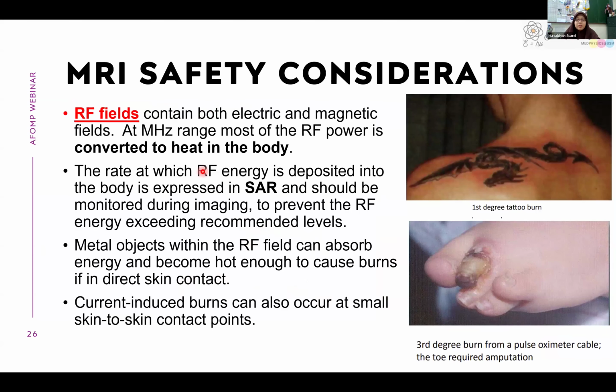In terms of radio frequency, as you know, it is EMF, so it contains both electric and magnetic fields. At the megahertz range, most of the radio frequency power will convert to heat in the body. The rate at which the radio frequency energy is deposited into the body is expressed as the SAR. In some of my interactions with radiographers and medical physicists, some of them didn't even know that MRI units have something called SAR. This is something I think we should be more aware of, because we should do this monitoring during imaging so that we can prevent the RF energy from exceeding the recommended levels.